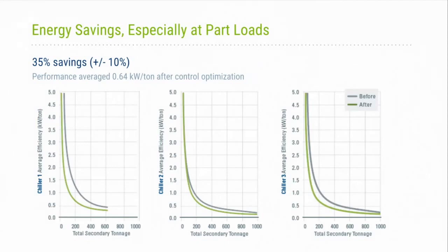You may have some technology already that's doing it as well, but if you have a plant that is struggling to get to that level of performance, this is on average, and what you see in the graph there is a representation of how the individual chillers performed. We would expect similar performance for each of the chillers. The lines there all show reductions. The gap between the before and after may be based on some maintenance or age issues between the chillers and some operational issues. Let's go to the next slide, please.